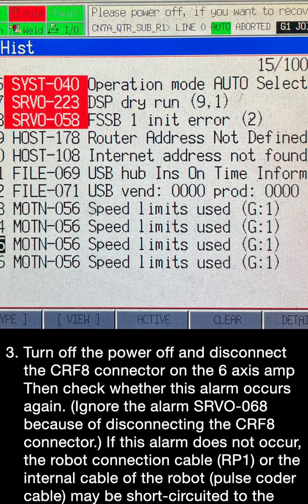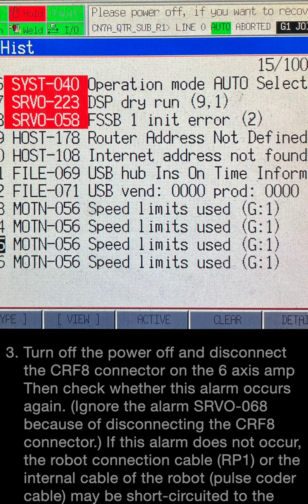Step 3: Turn the power off and disconnect the CRF8 connector on the 6-axis amp, then check whether this alarm occurs again. Ignore the alarm SRVO-068 caused by disconnecting the CRF8 connector. If this alarm does not occur, the robot connection cable RP1 or the internal cable of the robot pulse coder cable may be short-circuited to the ground. Check the cables and replace them if necessary.